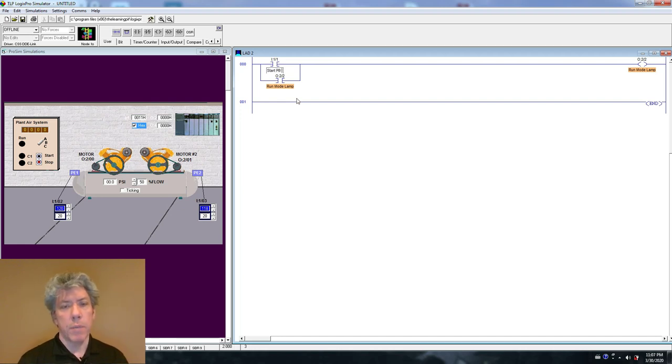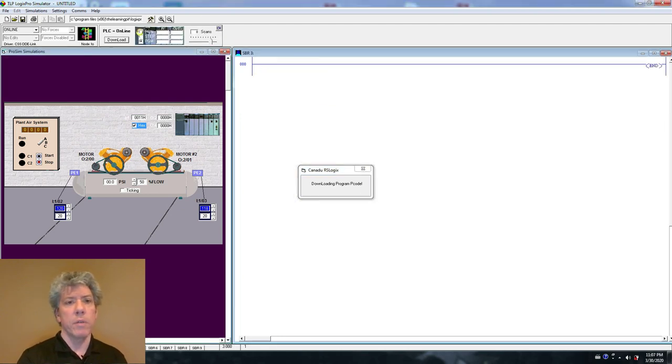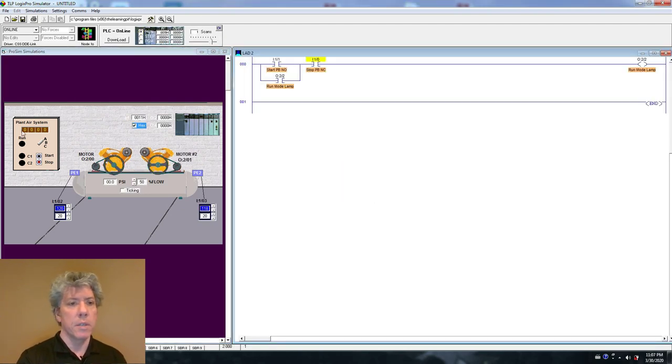In fact, start PB for push button, NO, that is normally open. Okay. So then the last thing I want is some way to stop it. And so we'll use the stop button for that purpose. And edit symbol, and this is the stop push button that is normally closed, NC. Now if I download this and run it, we've got a very simple seal-in circuit.